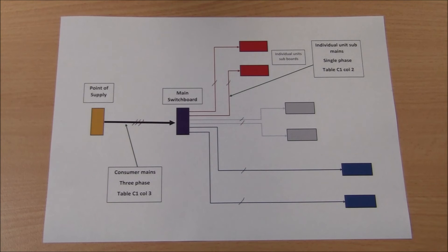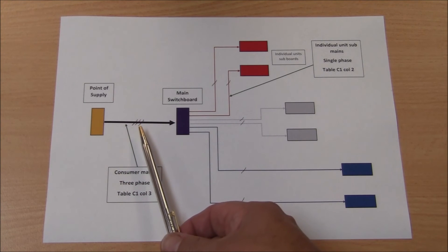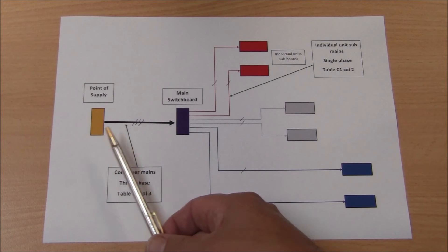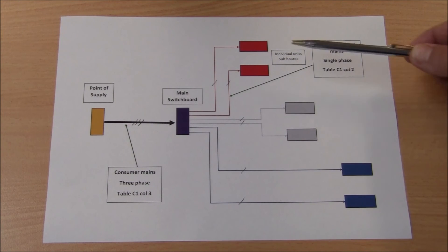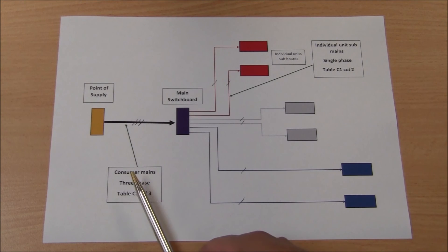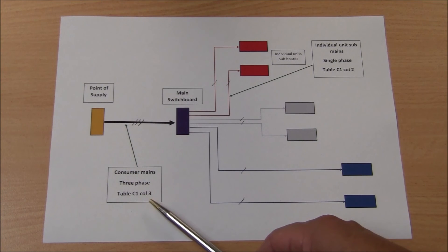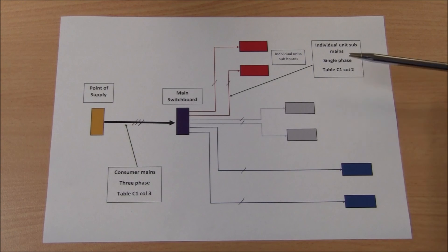Here we have a block diagram for the previous exercise: a three phase set of consumers mains. It goes from a point of supply to the main switchboard, and then the six units were split up evenly across the three phases—two on red, two on white, and two on blue. In this exercise we were looking to determine the maximum demand in the consumers mains, so for this part we will use table C1 column 3. For the individual unit sub mains, they would be single phase and would actually be determined by table C1 column 2.